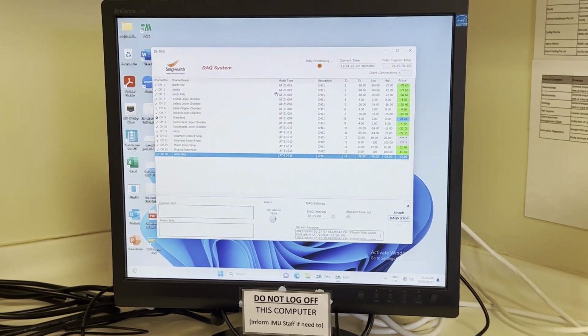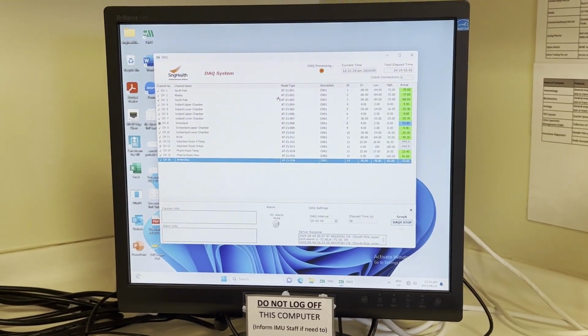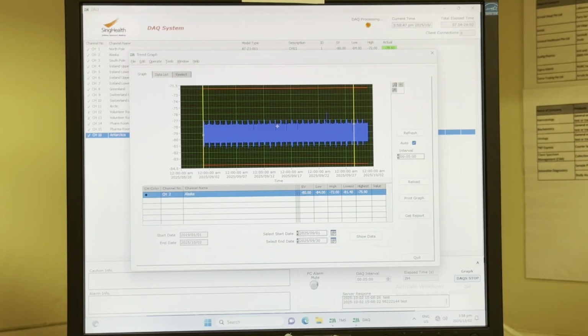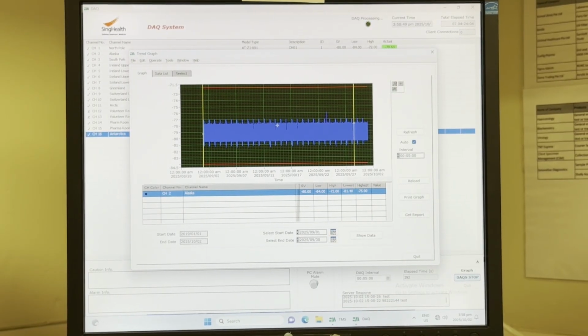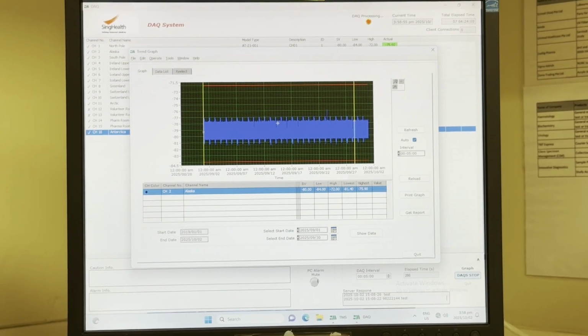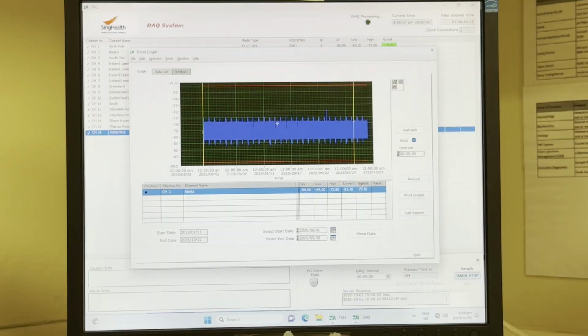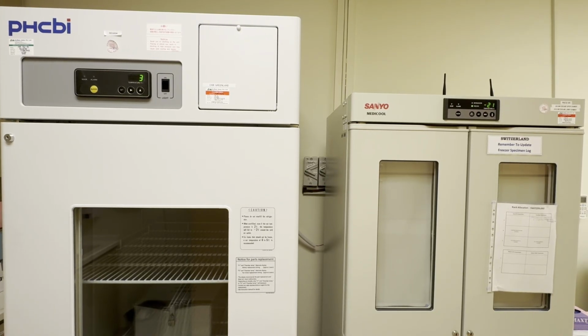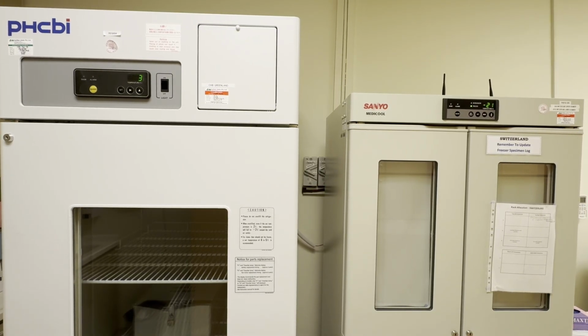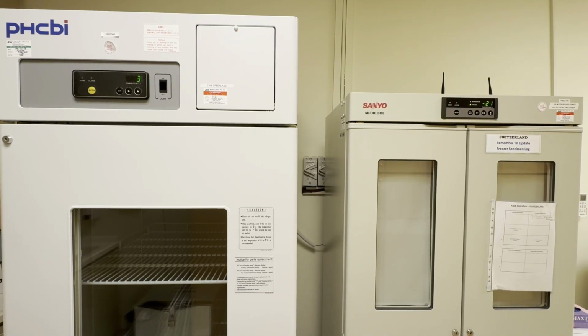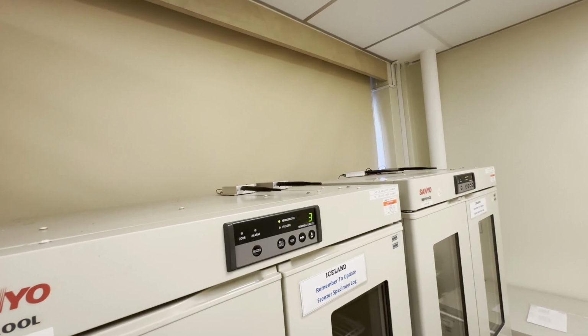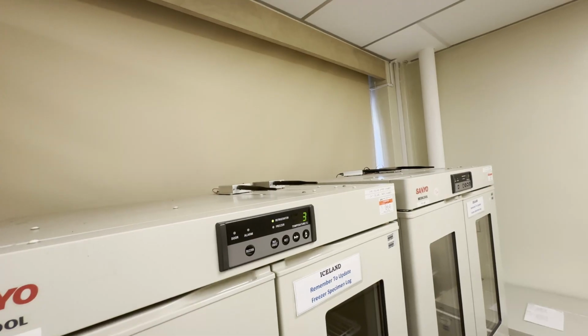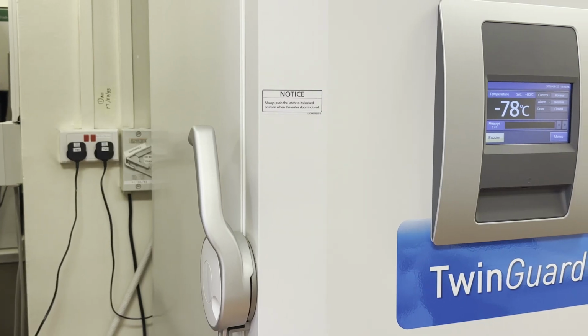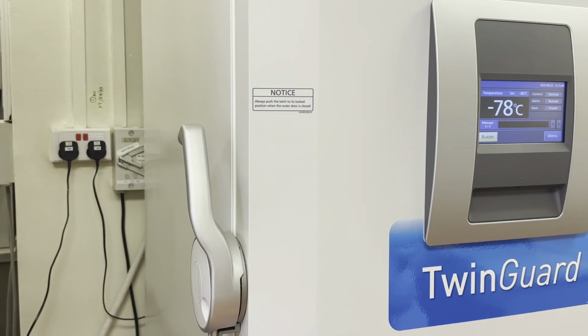The temperature of the fridge and freezer units is monitored electronically 24/7 by the Temperature Monitoring System, TMS. In addition to the TMS, all units are also monitored by the Hospital Facility Department, providing a 2-pronged temperature surveillance of the units. Calibration of the fridge and freezer units is conducted on an annual basis, whereas preventive maintenance is conducted every 3 months. The units are plugged into the hospital's emergency power supply, providing continuous power supply to the equipment in the event of a power failure.